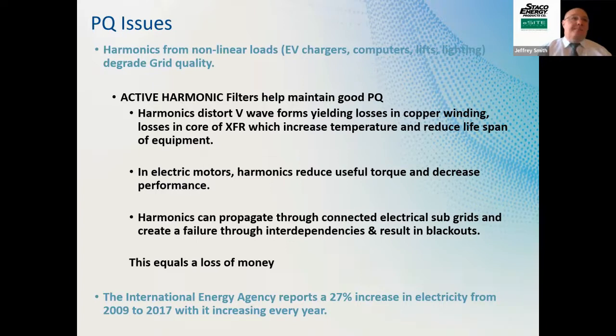Harmonic filtering. You look at harmonics, and that's just electrical noise on the lines. And with these harmonics, you're getting different levels depending on the type of system that you have out there. Drives, variable frequency drives, adjustable speed drives, they can cause harmonics back onto the grid. In electric motors, harmonics reduces the useful torque and decreases the performance. Well, these are the types of things we have to look at. Heat is one of the biggest issues with harmonics because it'll overheat some of your systems. And like it says, this all equals loss of money, because when you're losing it to heat, you're just wasting electricity. Next slide.